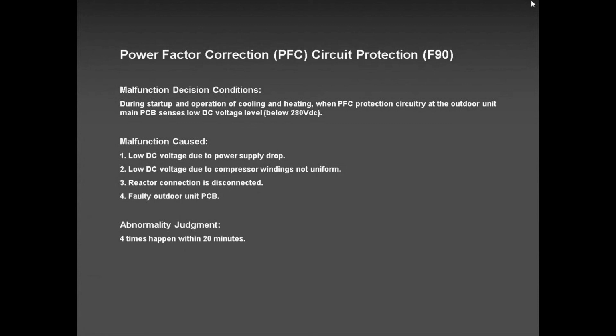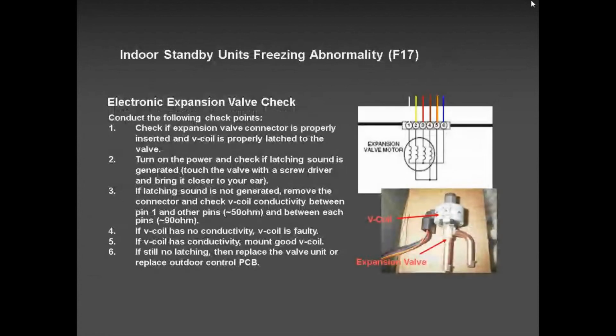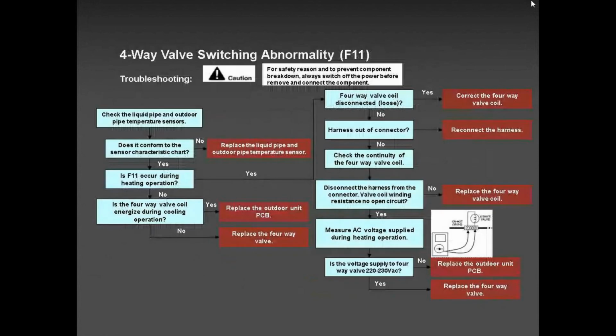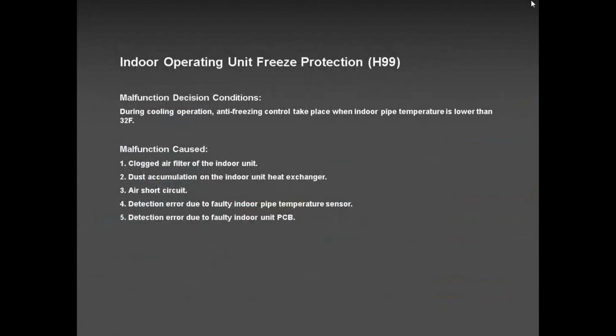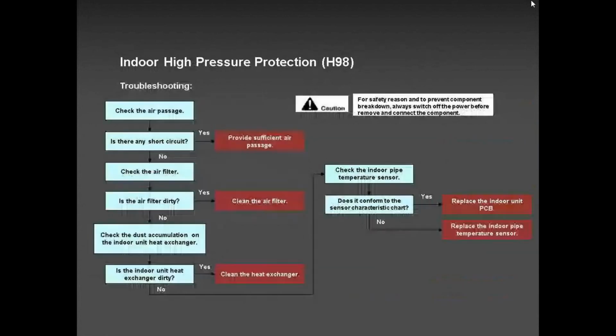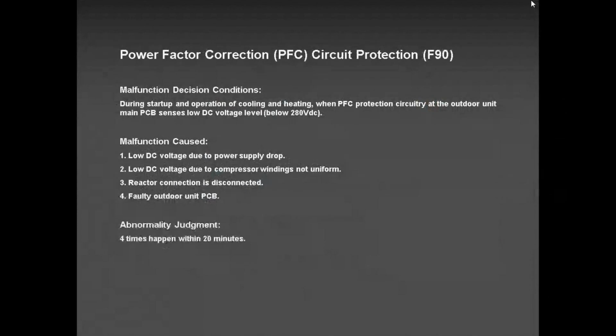F17, this is the error code I mentioned to you. You will not see this error code in single zone. You will only see it in multi-zone. That's when you cross the wire, when unit A went to B, B went to C. That's where you'll have the unit freezing, especially when the homeowner turned it off. So the moment you see F17, please keep that in mind. You have crossed the wire.